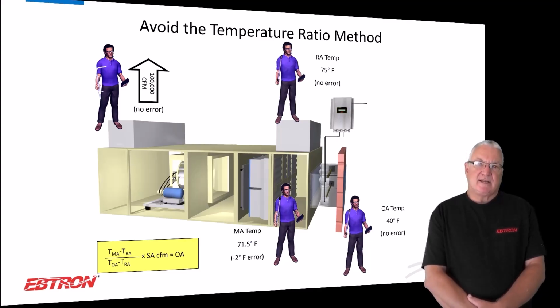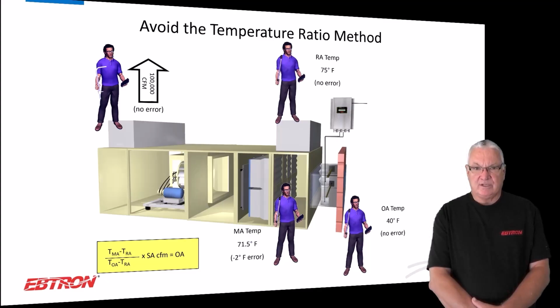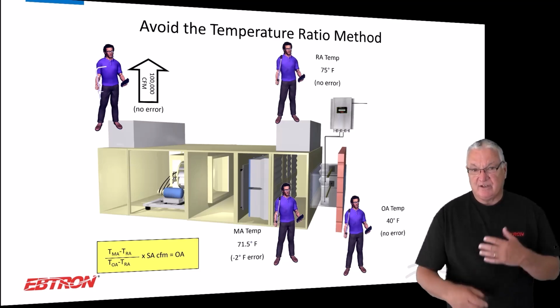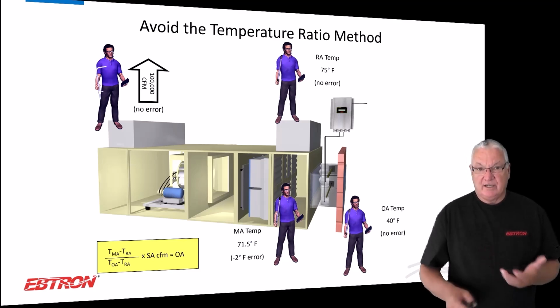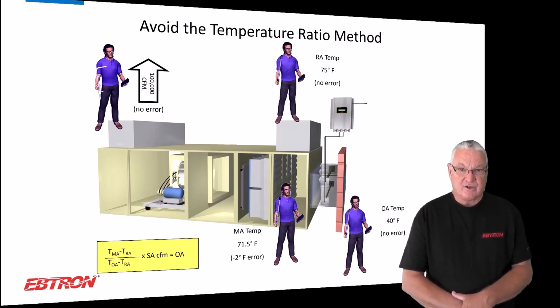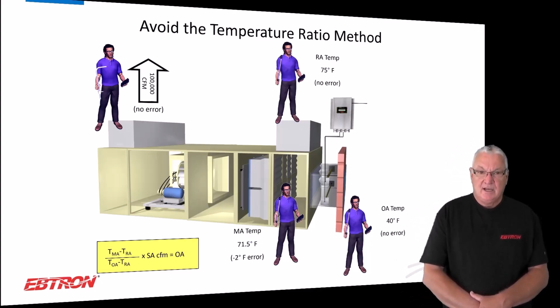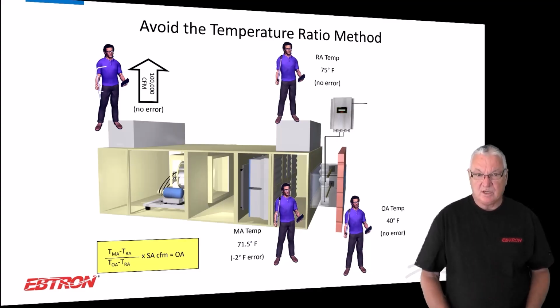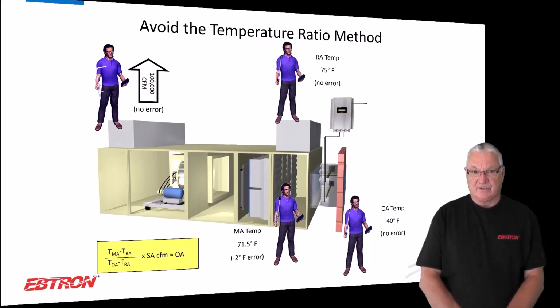But the mixed air is not easy to measure accurately. In fact, I can show you with velocity weighted temperature that you could be a few degrees off in some cases, because you have a huge velocity profile and a huge temperature profile that you're trying to measure, particularly with return air and outdoor air. So I'm going to say that the mixed air measurement had 2 degrees of uncertainty, which I don't think is a lot. I think it's actually more than that.